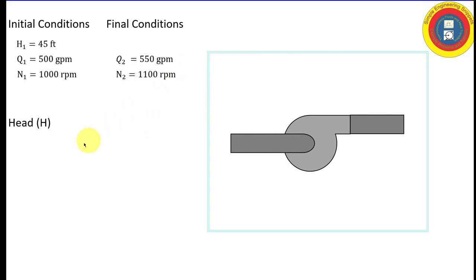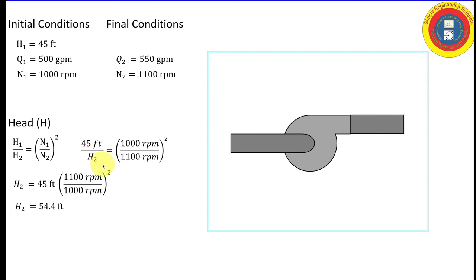Now let's work on head. Again, it's a quadratic relationship. Solving it for the new pump head, we get that the final pump head is 54.4 feet. And that is our final answer.